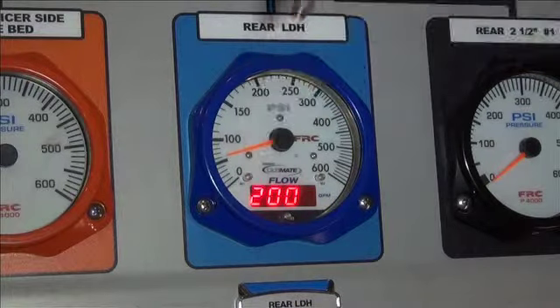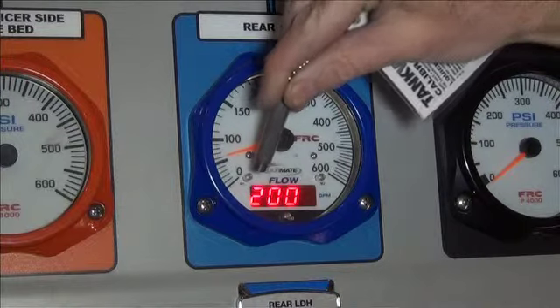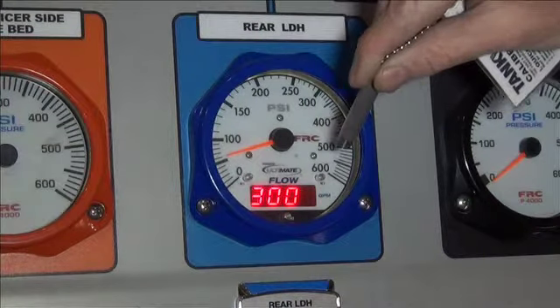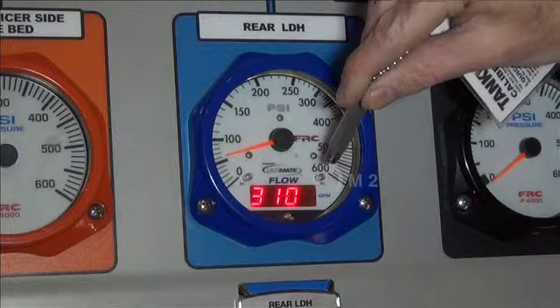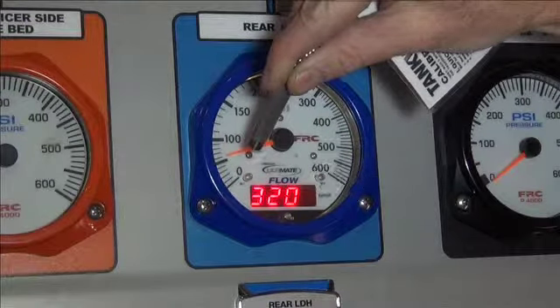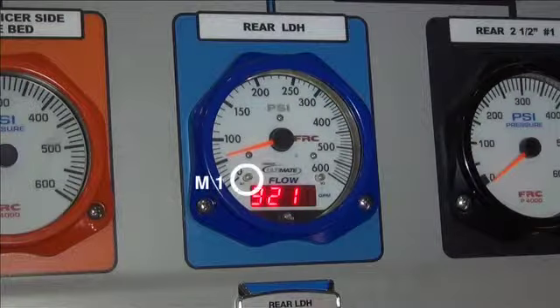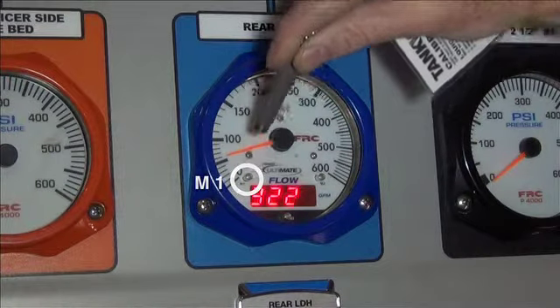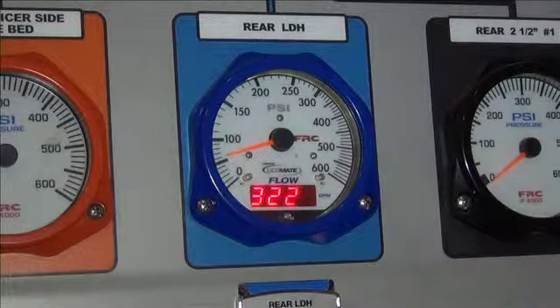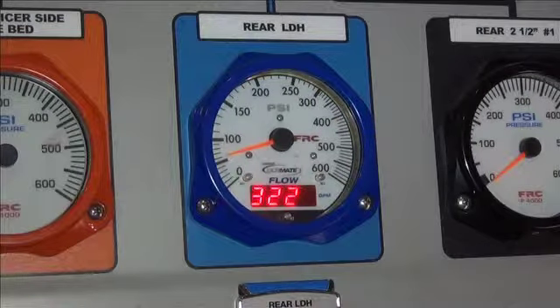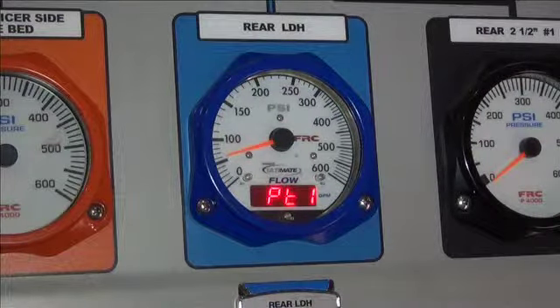Touch the M1 sensor twice more to change the first digit to a 3. Touch the magnet to the M2 sensor twice so that the second digit becomes a 2. Now touch the magnet to the M1 sensor twice so that the third digit becomes a 2. You have now accessed the multi-point calibration program which displays PT1. The flow meter is now ready to have the first calibration point set.